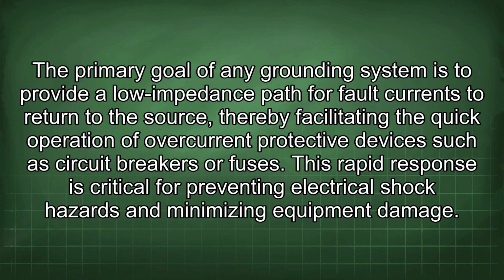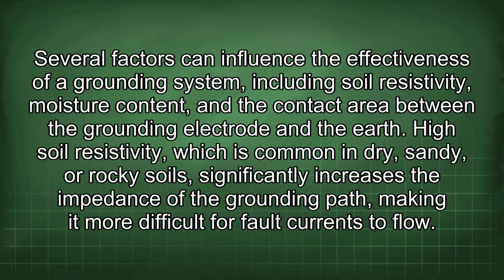The primary goal of any grounding system is to provide a low impedance path for fault currents to return to the source, thereby facilitating the quick operation of overcurrent protective devices such as circuit breakers or fuses. This rapid response is critical for preventing electrical shock hazards and minimizing equipment damage. Several factors can influence the effectiveness of a grounding system, including soil resistivity, moisture content, and the contact area between the grounding electrode and the earth.